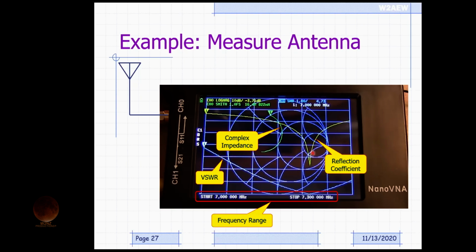So this is the reflection coefficient. Again, reflection coefficient and SWR are mathematically related to each other, so they're both going to give you the dip at the same point. It's often easier to see the location of that dip on a log magnitude reflection coefficient plot as opposed to SWR. It's very easy to see where that point is. It's a little bit shallower on the SWR plot. And we can tell that is a reflection coefficient because it's on channel 0 and looking at log mag.